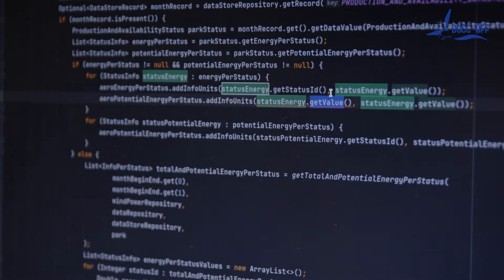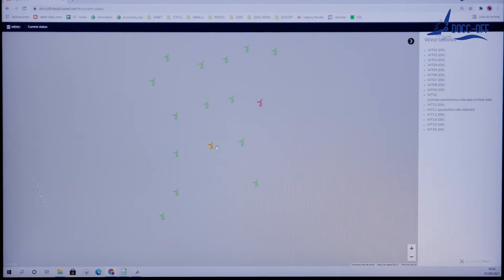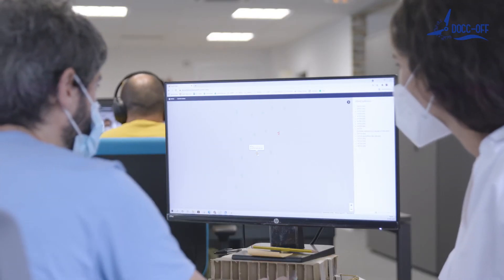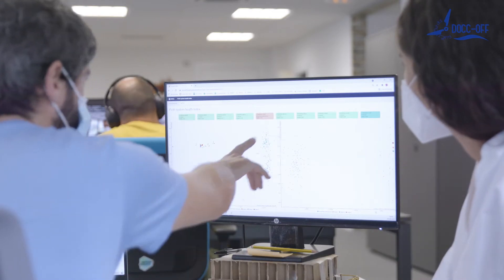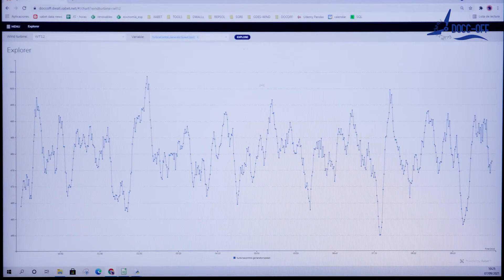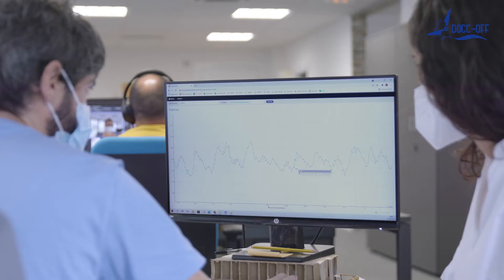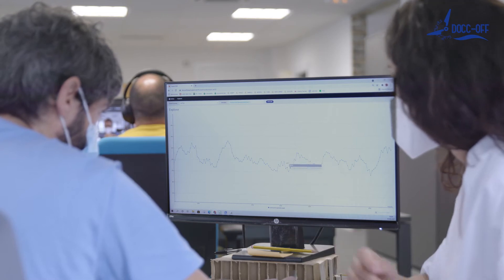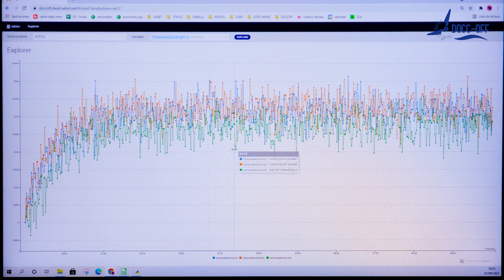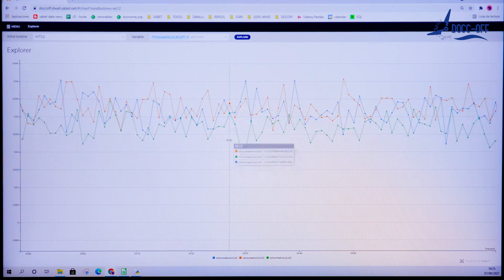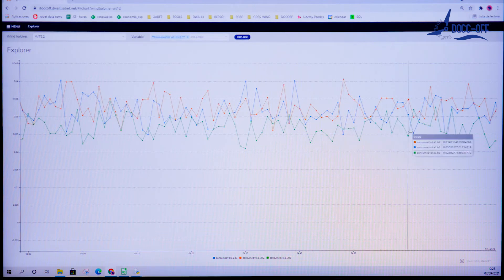DOCOFF has developed a specific digital platform to monitor hydraulic pitch system health. Wind farm operators will be able to monitor the wind farm using a map screen. Whenever a potential issue is detected, the wind turbine's icon will change its color. Clicking on pitch system health, its evolution will be shown. Hydraulic system flow health, cylinder speed, and cylinder-accumulated flow differences are plotted for each blade against failure regions. If any of them fall into a potential failure zone, maintenance is recommended. In addition, specific variable analysis is available.